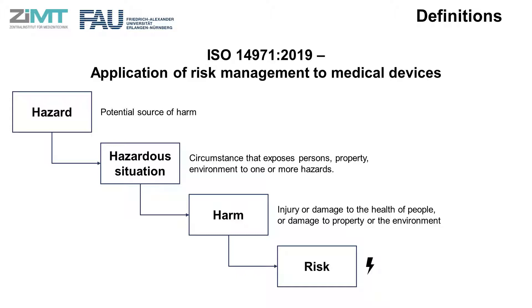Before we dive into ISO 14971, we need to further understand some definitions. We have already defined risk management and risk, but there are three other important definitions to understand. These are: hazardous situation, which is defined as a circumstance that exposes people, property, or environment to one or more hazards; where a hazard is defined as a potential source of harm; and harm is defined as an injury or damage to the health of people, or damage to property or the environment.